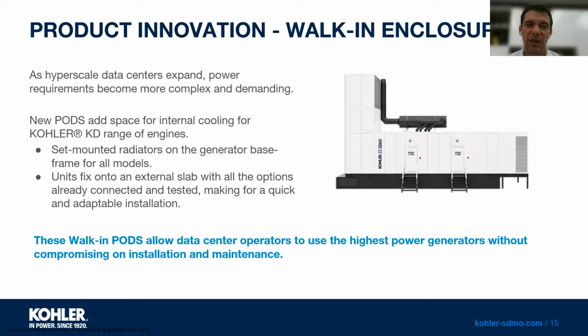This allows us to bring the units to site in modular form, with the main walk-in enclosure delivered as a unit, then mounted on the external civil works concrete slab with all the options already connected and tested, allowing for a quick installation with minimal site time and man hours. This allows data center operators to use the highest power machines available without compromising on their requirements for long-term serviceability, operation and maintenance of those units.